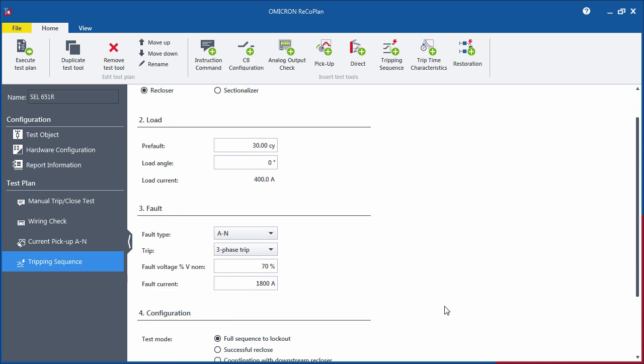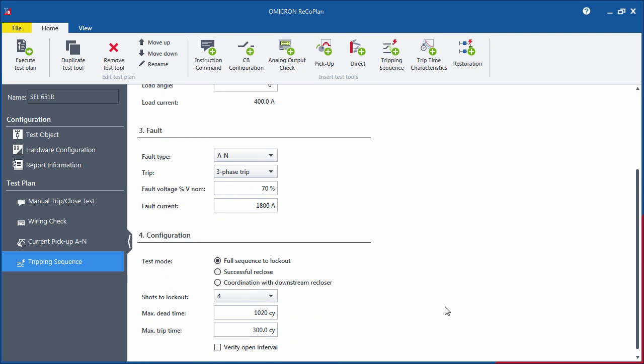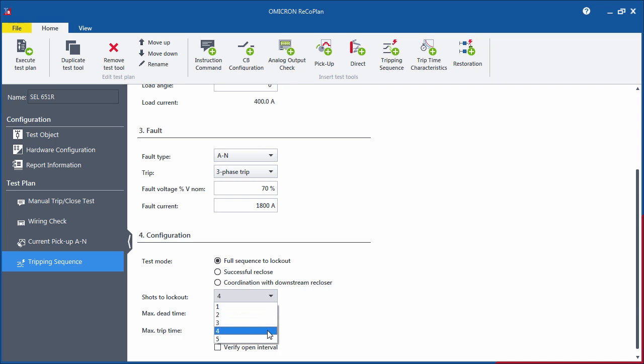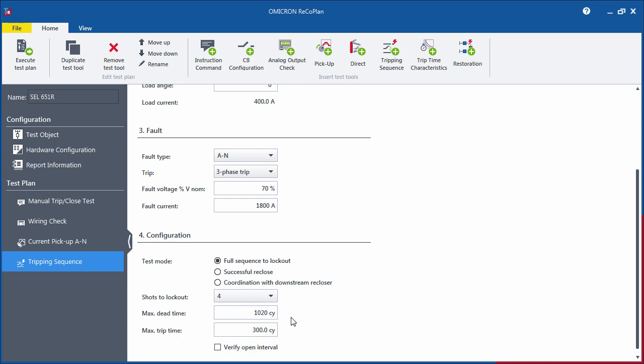In the Configuration section, you can choose the number of times that the controller trips and recloses before entering the lockout state. The maximum dead and trip times have to be adjusted according to the parameterization of the recloser control. The test will be aborted if the respective signals are not measured within these two time values.